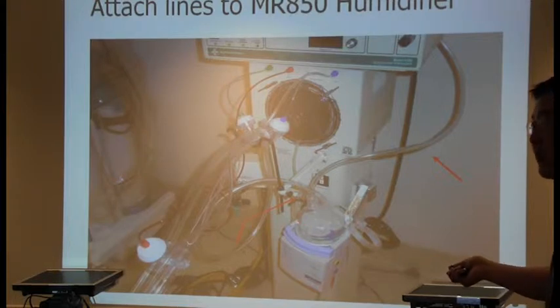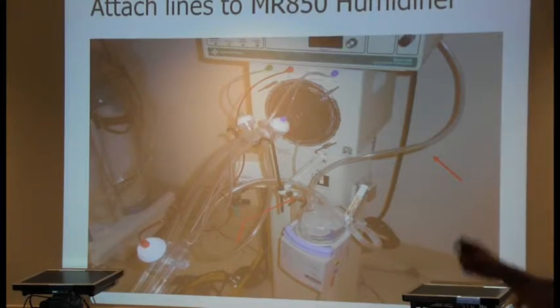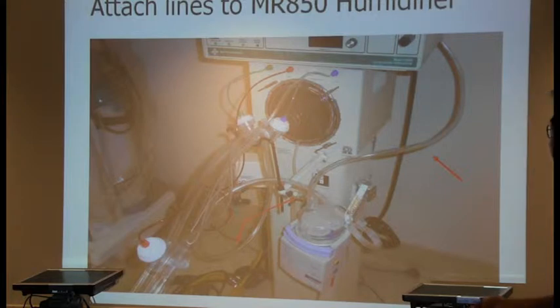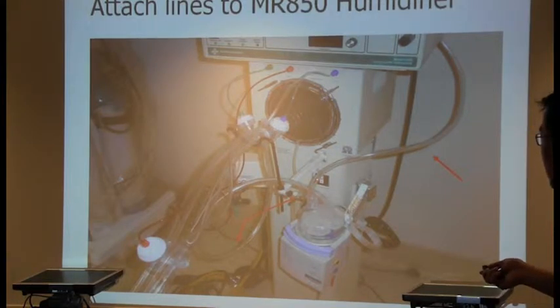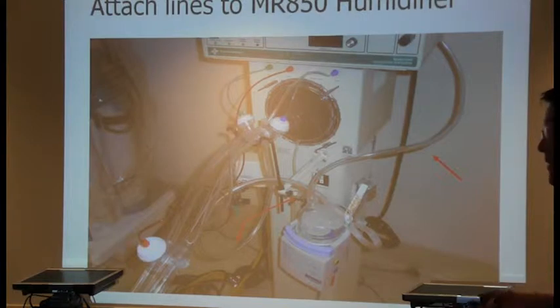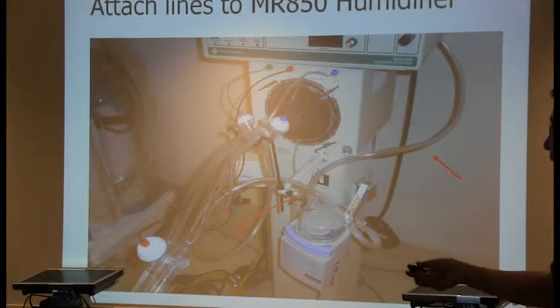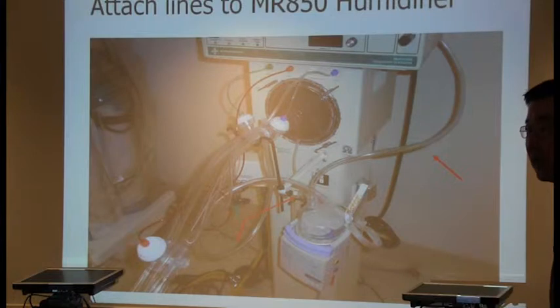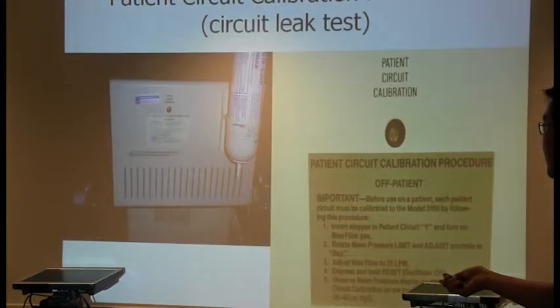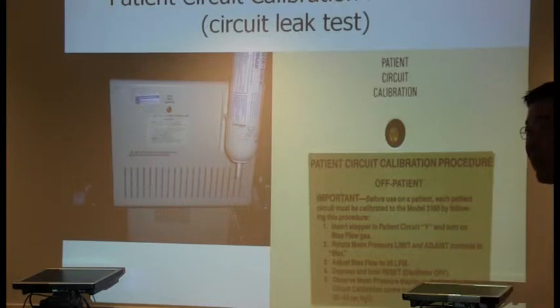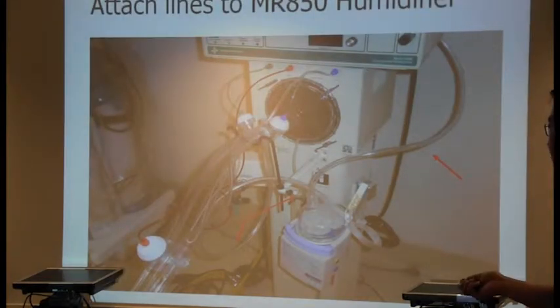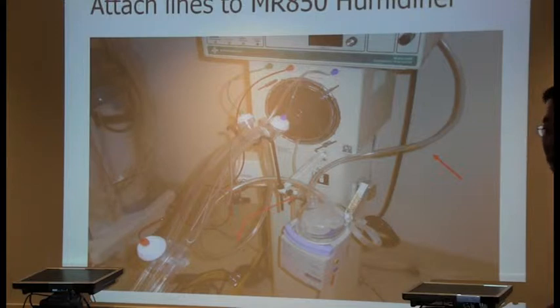Also, if you think your water chamber is perfect, they're not. These things have cracks as well. So what you can do is take this tubing and the tubing here and get a 15mm adapter and bypass your water heater, the chamber, and do your test. And when you do your test and you come within 39 to 43, that tells you that your water chamber is bad, so get a new water chamber. Replace it. Okay?